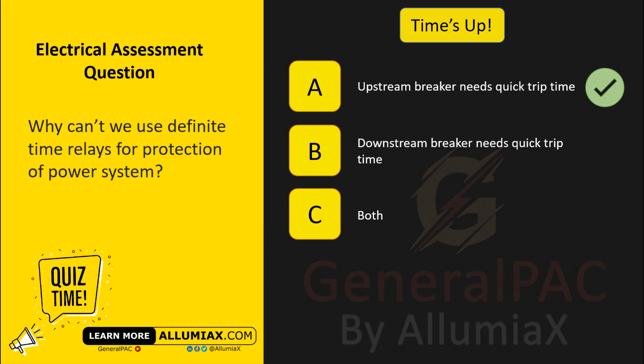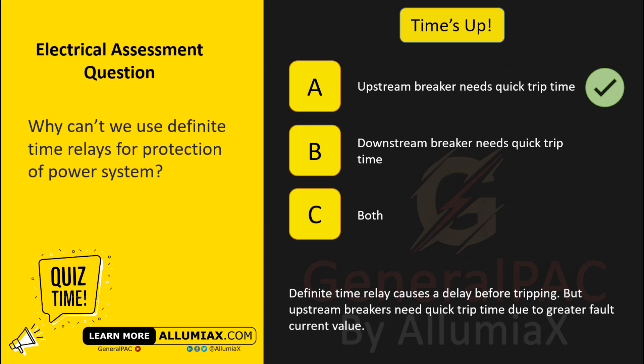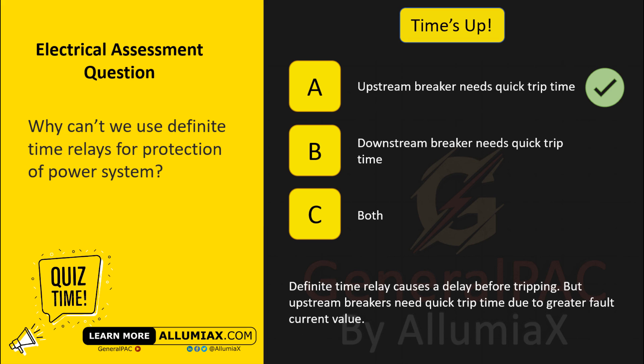The answer is A. Definite time relay causes a delay before tripping, but upstream breakers need quick trip time due to greater fault current value.